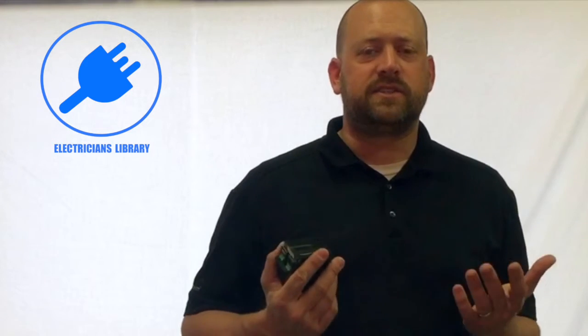The AIC is a safety rating, and it's independent of the nominal load rating of the overcurrent protection device or the panel. It has nothing to do with the ampere rating on the handle of the breaker.